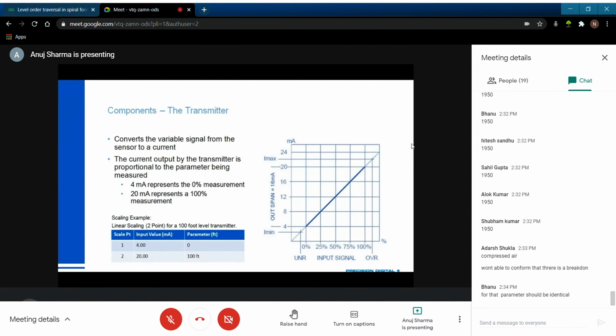So what the transmitter does is say, all right, it's developed so that at 0% of whatever its measurement range is, you're going to get 4 milliamps. And at 100% of whatever its measurement range is, you're going to get 20 milliamps. Most of the time, those 2 points are connected by just a simple linear line.